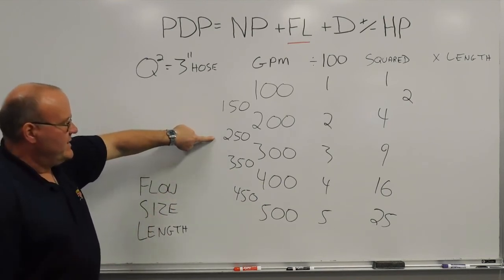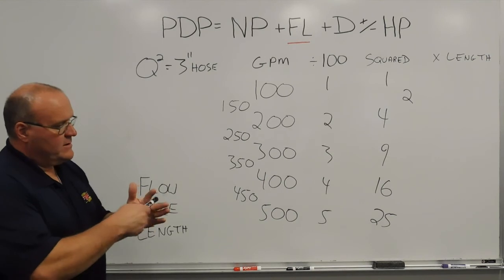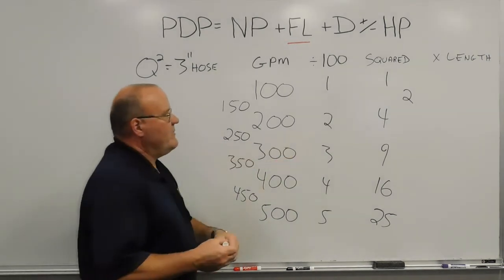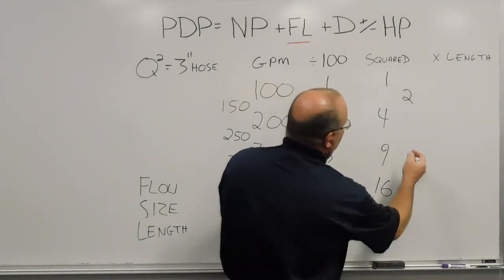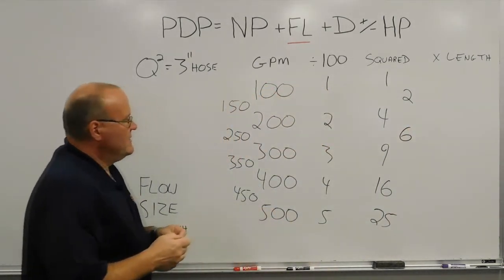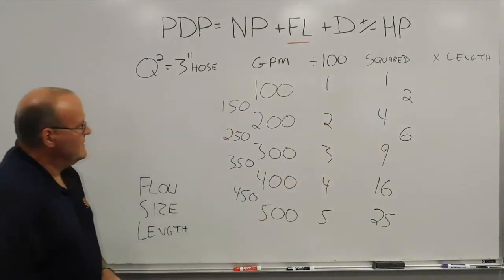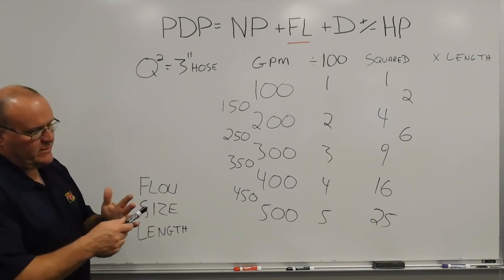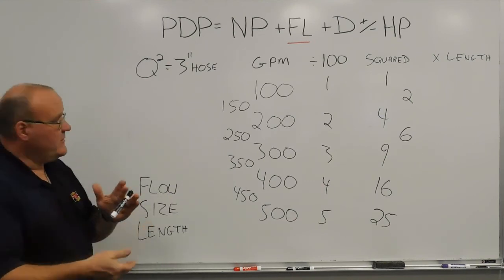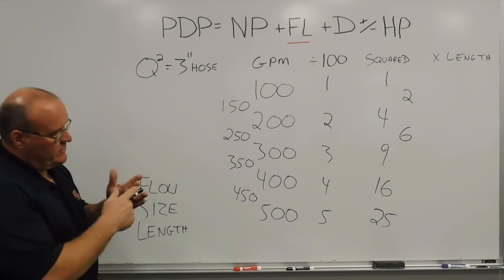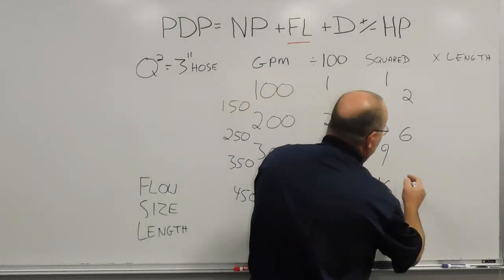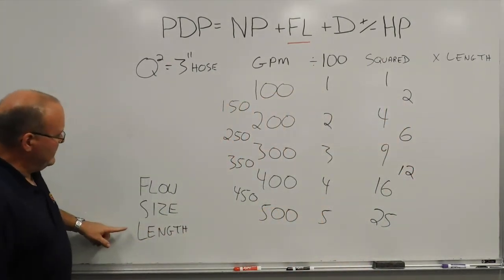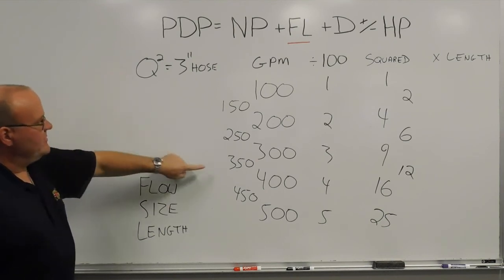For 250 gallons a minute: 100, 200, 300 — 250 falls between 2 and 3. Cross-multiply 2 times 3 gives 6. So for every 100 feet of 3-inch hose flowing approximately 250 gallons a minute, that's 6 pounds of friction loss. For 350 gallons a minute: 100, 200, 300, 400 — 350 falls between the two. Cross-multiply 3 times 4 gives approximately 12 pounds of friction loss for every 100 feet of 3-inch hose flowing 350 gallons a minute.